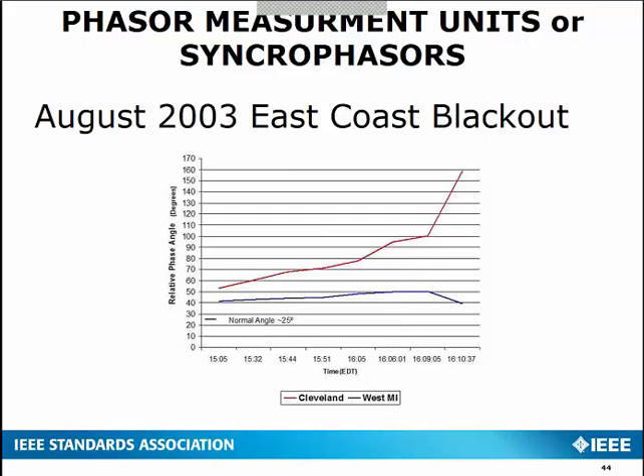A good example of when I talk about measuring power between two areas is the phase angle. A normal phase angle between two areas within an interconnected system is 25 degrees. Using phasor measurement units in 2003, you can see that around 3:50 in the afternoon, the Cleveland system and the Western Michigan system began to exceed that 25 degrees. Well, this was approximately 20 minutes before the system completely separated. With PMUs, it gives the operators much more time to take action as the system fully separates.